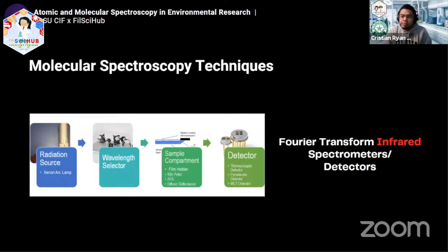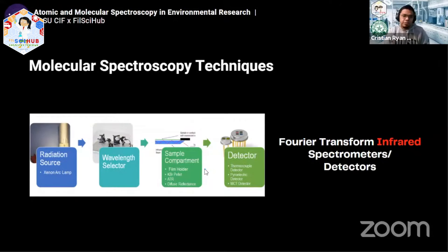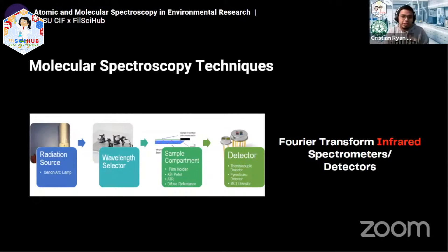The FTIR, or Fourier-transform infrared spectrometer, looks similar to what we saw earlier but this is what's inside. This has to be corrected — it's not a xenon arc lamp; it's usually a heat source, typically in ceramic form, because infrared light requires a heat source. We also have a wavelength selector — which we'll see in the next slide — it's not like a filter but more like a monochromator. There are various sample compartments depending on the sample, and there's a detector that is not a photodetector since we're dealing with infrared light, not UV or visible. The commonly used one now is the pyroelectric detector.